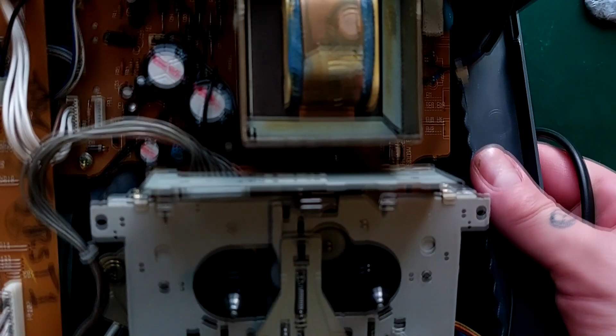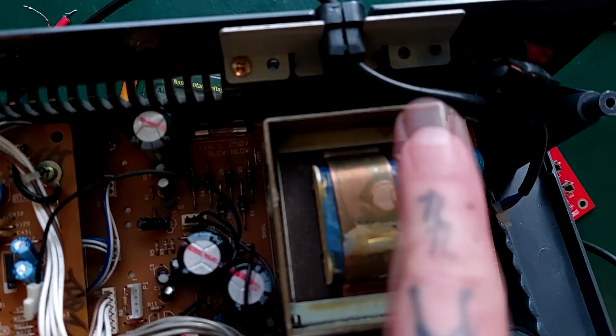You could use the meter here to test for the presence of AC, to make sure the AC coming in via this cable is getting to the primary side of the transformer, or out the other side to the secondary. But you could also use a continuity tester with the unit turned off to check the coil is still intact. These diodes used for rectification, there's four of them down here - you can use the diode tester for that. So there are other ways of testing everything without putting your probes near a high level of AC.